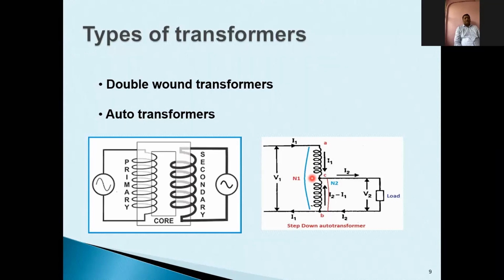So in auto transformers, basically, there will be some part of the winding which will be common to both primary and secondary. And there will be some number of extra turns electrically connected to that common part, the series winding, which will be called the secondary winding. So the lower number of turns will form the LV part, and the lower number of turns plus the extra turns, which make the number of turns more, will form your HV part of the winding. So your lower number of turns part, called the common part, will be the LV side, and combined both will be the HV side. So this is called the auto transformer. Next slide, sir.